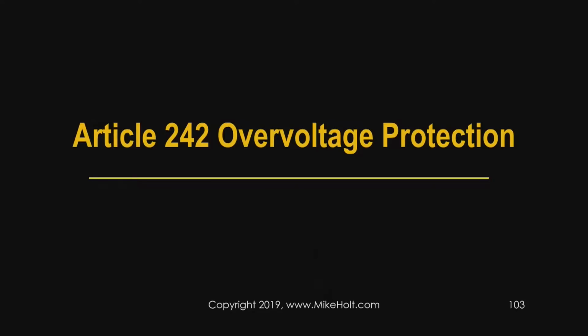Okay, Article 242, Overvoltage Protection. This is a change in the 2020 National Electric Code, where we previously had two articles dealing with lightning arresters and surge protection devices. Both of these work on similar principles: when there's an overvoltage, the device takes some action to reduce that overvoltage event. Article 242 has now combined those two articles into one.